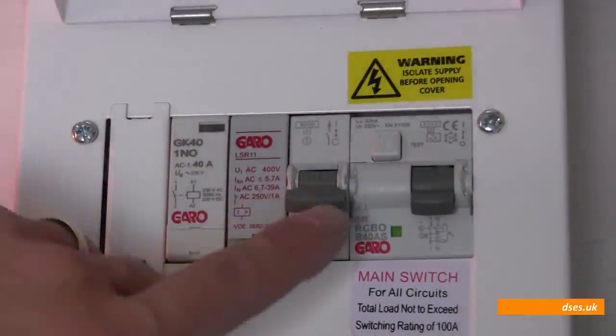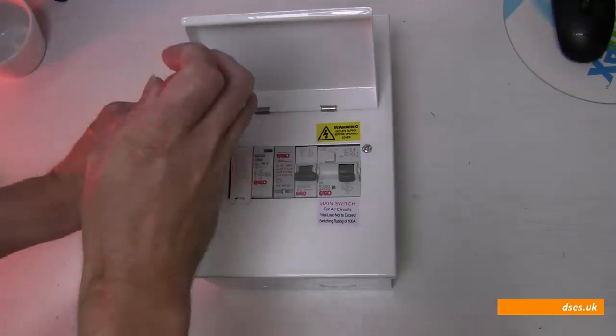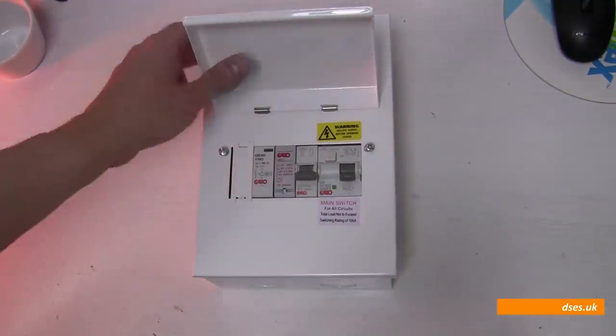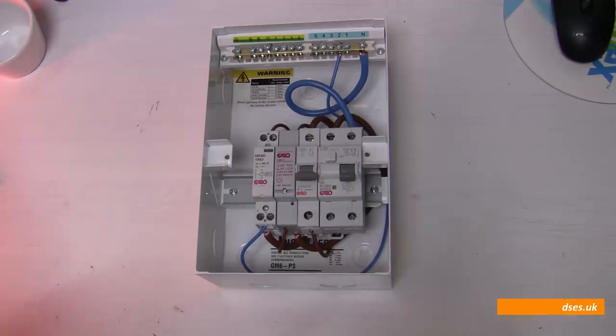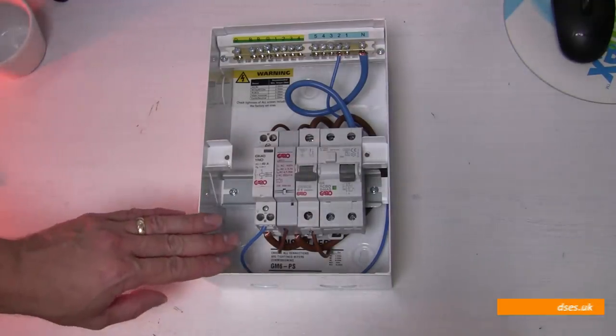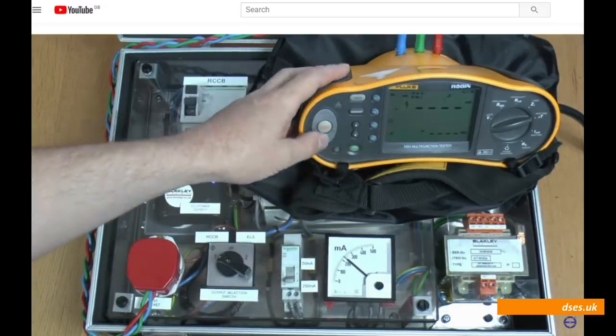Let's flip the old lid and we have here a Type A RCBO. We have a Type A RCBO, which is interesting as Garo tell me they've been using Type A for years. If you don't know about your RCD types, Type AC is what you'll find in most consumer units to date. However, they're rapidly falling out of favour because DC current getting into them can stop them from working — so probably best not to use these with things like vehicle chargers. For more information on DC in AC RCDs, point your browser at the E5 channel where the dream team of Paul Meenan and John Maud demonstrates just why AC are out, and Type A or B are now the big noise in additional protection, and why manufacturers are all switching over to them.